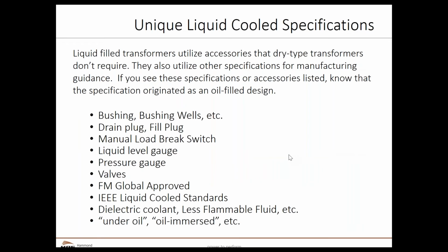So when we look at a specification for liquid filled, sometimes the transformer specification doesn't actually say liquid filled, or sometimes it does, but you have to kind of get into it. There are some clues, though, that will key us into liquid filled. When we hear the words bushing wells, anything that says bushing, anything that says drain plug or fill plug, again, these are typically associated with liquid filled units. That will tell us it's a liquid filled transformer specification.